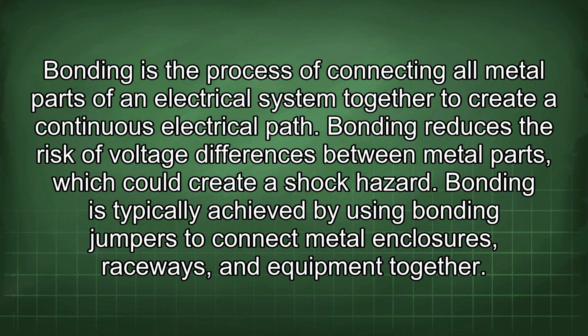Bonding is the process of connecting all metal parts of an electrical system together to create a continuous electrical path. Bonding reduces the risk of voltage differences between metal parts, which could create a shock hazard. Bonding is typically achieved by using bonding jumpers to connect metal enclosures, raceways, and equipment together.